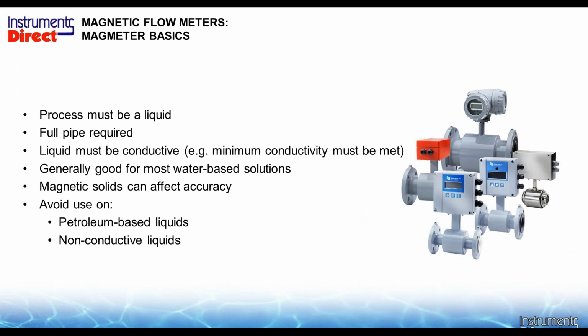What are the gotchas with a magnetic flow meter? Well, today it's limited to liquid applications. And we pretty much need a full pipe application with the models that we're talking about. And the liquid needs to be conductive. So that's really the gotcha as far as the separations of different liquids. We need to have a minimum conductivity of about 5 micromhos or 5 microsiemens, depending how you look at it, as far as conductivity.